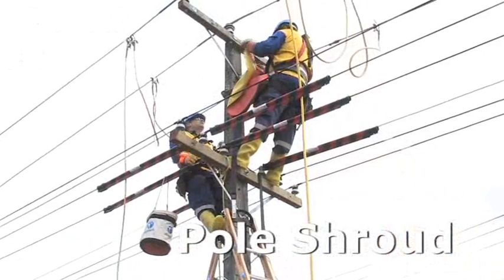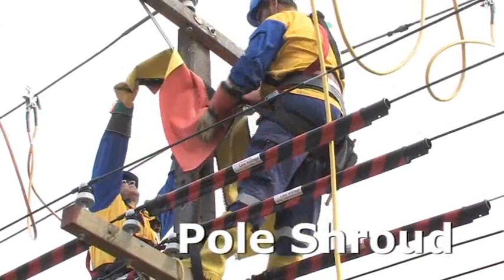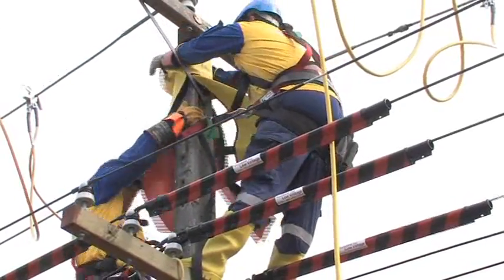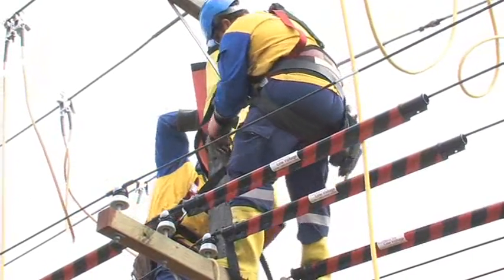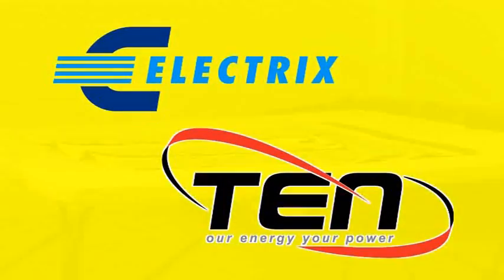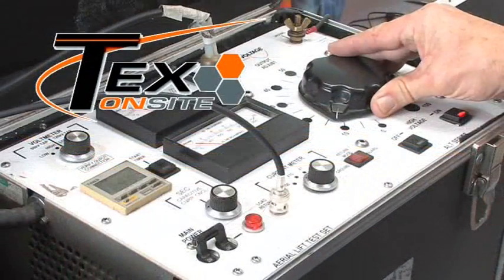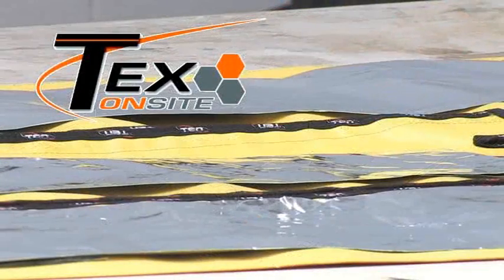The primary role of the pole shroud is to protect the worker from the potentially conductive pole. When used in conjunction with the dielectric boots and gloves, this meets the requirements of the ESI handbooks. We developed the pole shroud in conjunction with the energy network. It's been tested by TEX OnSite at 10 kV for one minute, giving it a class 1 working voltage of 7.5 kV.